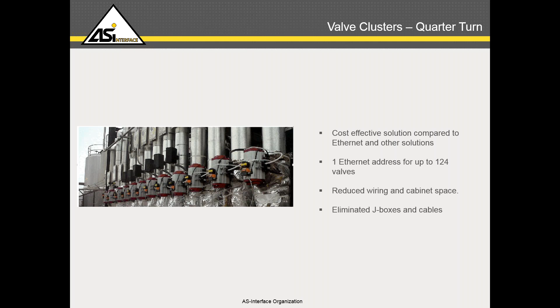We did a cost study on these valve clusters, comparing conventional valve head wiring to a bus system like DeviceNet, and then comparing that to the ASI bus. The valve head itself is pretty comparable in cost to conventional heads, a bit more expensive, but not nearly as expensive as an Ethernet/IP or DeviceNet head. Outside of hard costs, what you're really saving is installation labor, since it's much simpler to run the two-wire flat cable than a DeviceNet cable or large wiring bundles.